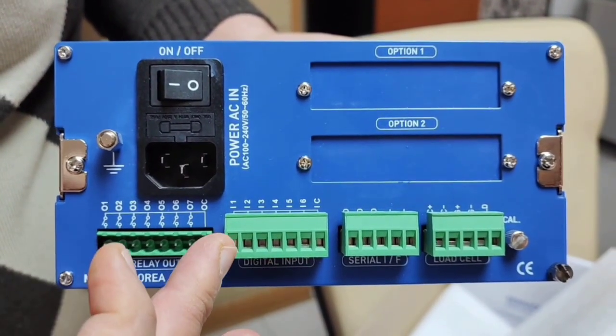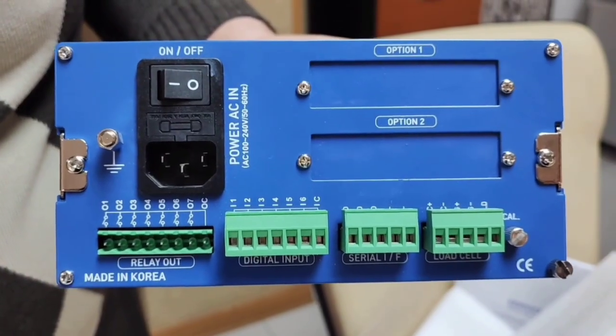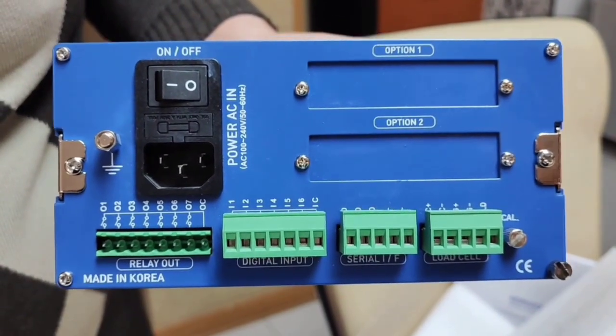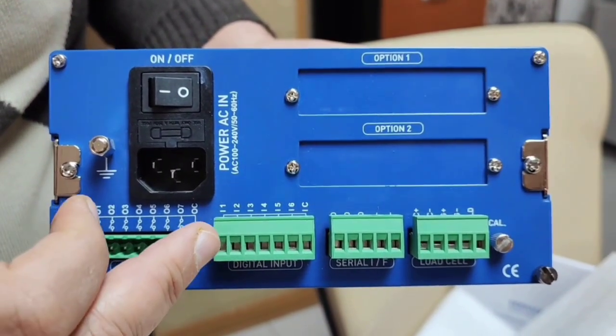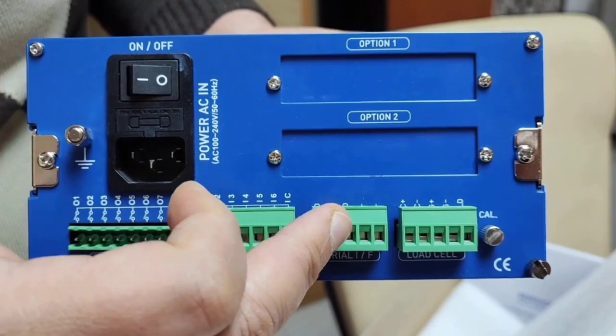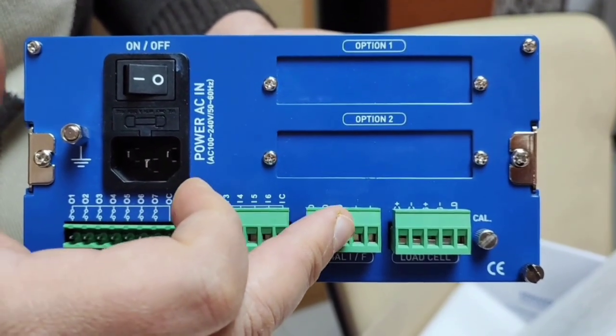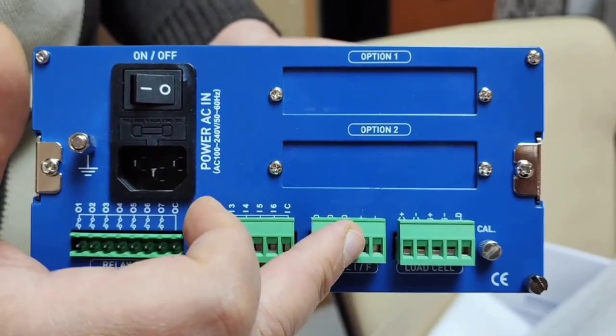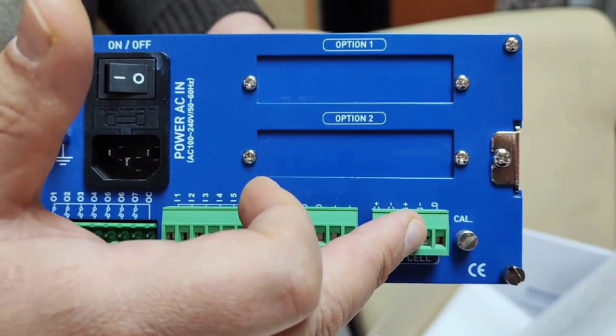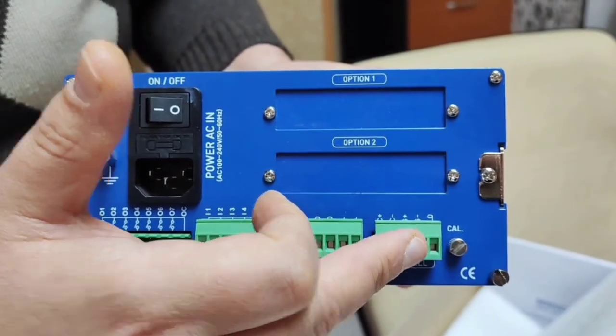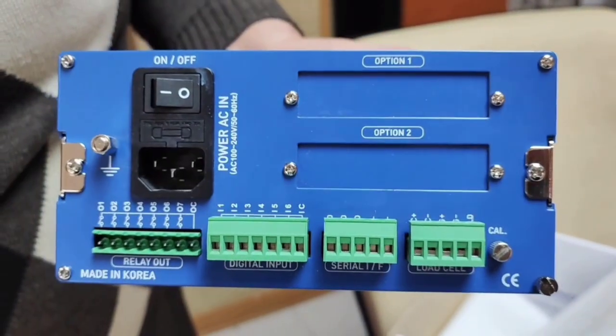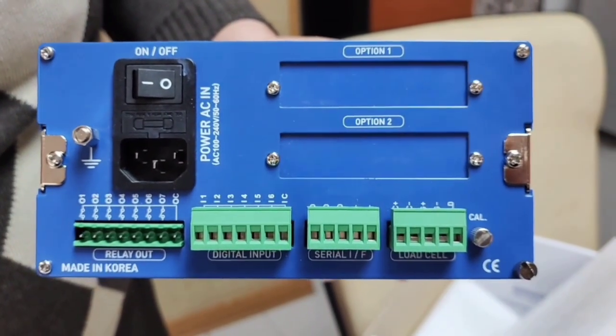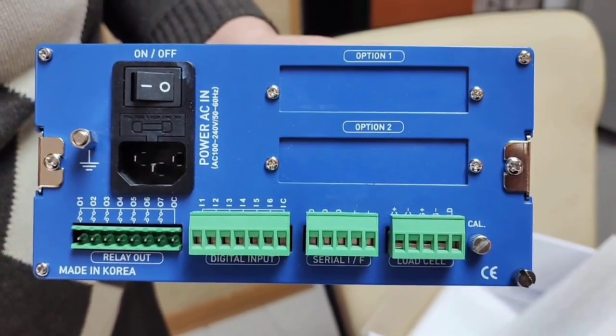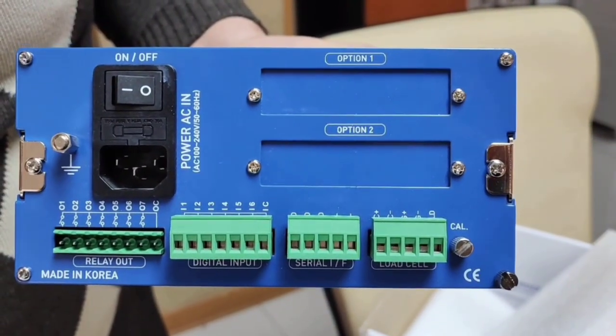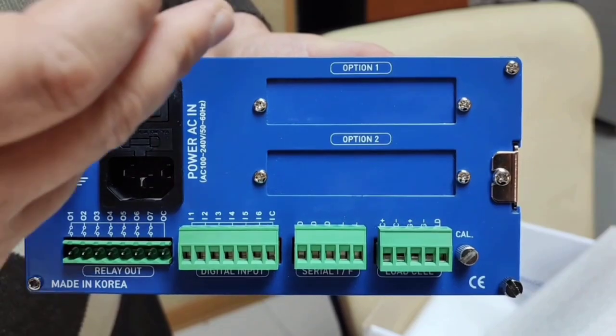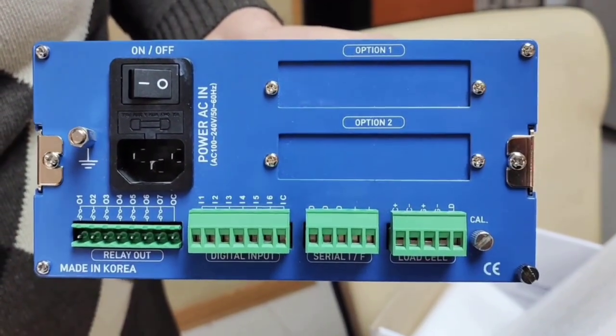For example, we can set input 1 to perform a zeroing operation for us, or set input 2 to trigger a print command, for instance. Now, according to the tables provided in the manual, we can configure these inputs. This section is related to the RS-232 serial port, which allows us to use this terminal for RS-232 output. This part is for the load cell input, where we can connect the load cell to the device using this terminal. We have 2 option cards, and this device supports various option cards. For example, we can easily incorporate and install an RS-485 serial network communication option card directly into it. Or for another instance, we could add a high-capacity memory card, which will automatically store all of the recorded weight values in a standard Excel spreadsheet format for us to review later.